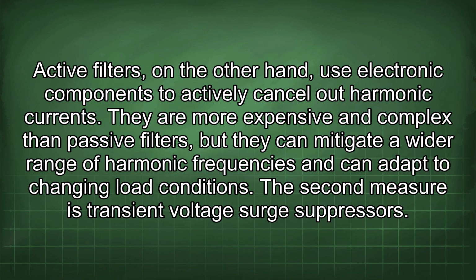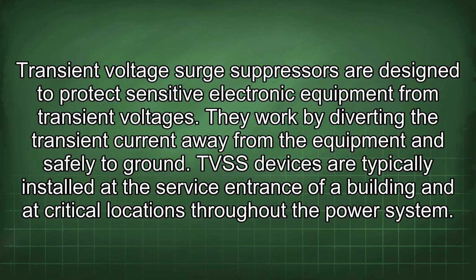The second measure is transient voltage surge suppressors. Transient voltage surge suppressors are designed to protect sensitive electronic equipment from transient voltages. They work by diverting the transient current away from the equipment and safely to ground. TVSS devices are typically installed at the service entrance of a building and at critical locations throughout the power system.